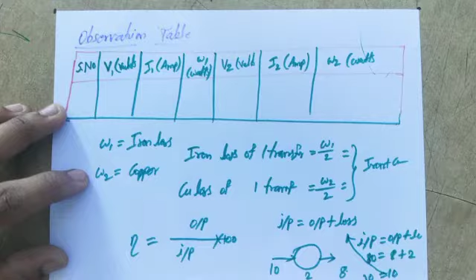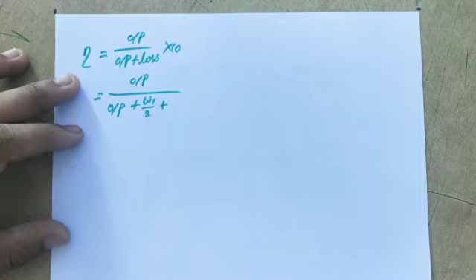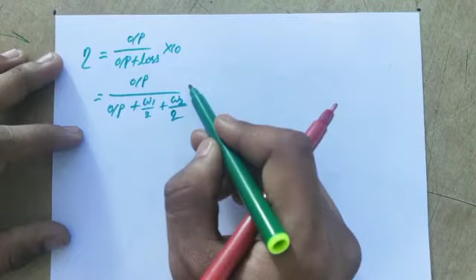So we can write input equals output plus loss. Efficiency equals output by output plus loss into 100. In this case, the losses we have are two: iron loss of the transformer is W1/2 plus copper loss of the transformer is W2/2. If you use this in the formula and multiply by 100, we can calculate the efficiency of the transformer.